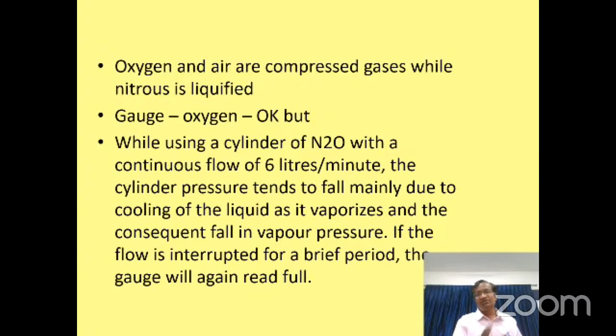But what happens in nitrous oxide? There is a liquid, so there is vapor in the cylinder upwards. As soon as you open the nitrous oxide and give the flow to the patient, the upper vapor portion will go to the patient and slowly the pressure seems to decrease because the pressure is caused only by the gas. Now you leave it for some time. Again it vaporizes and the pressure will come back to normal. So that is what is being told here.